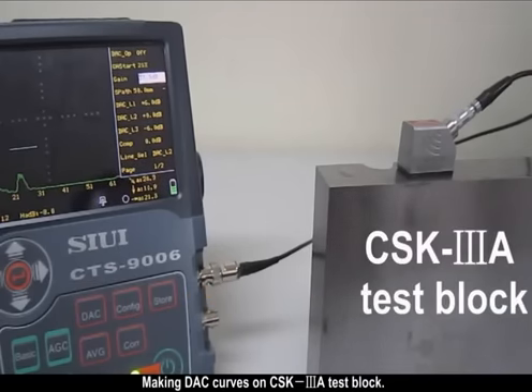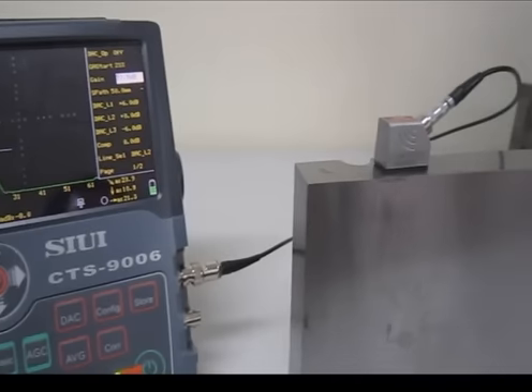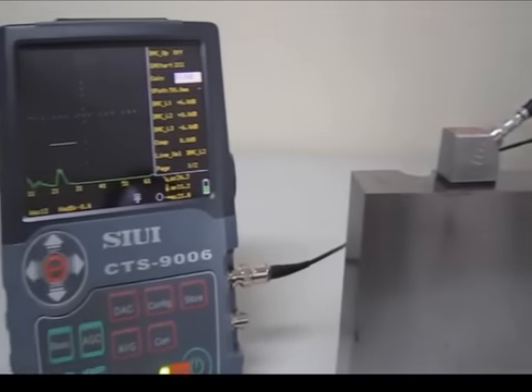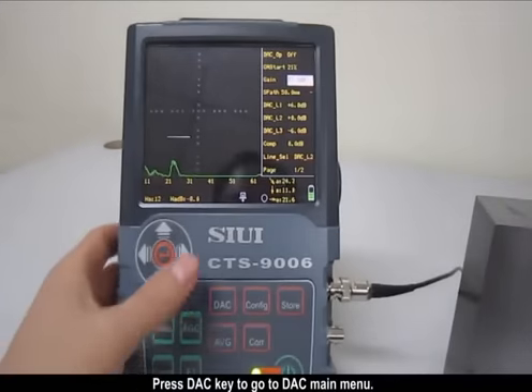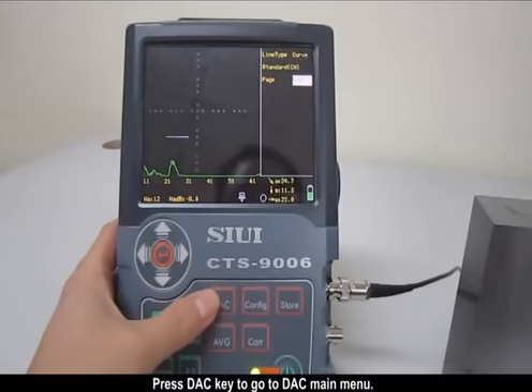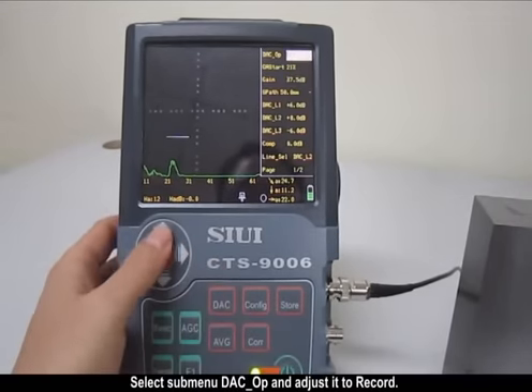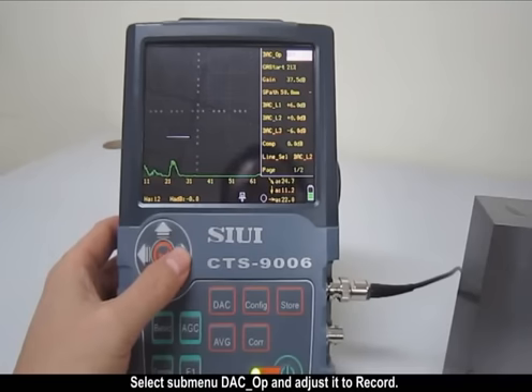Making DAC curves on CSK3A test block. Press DAC key to go to DAC main menu. Select submenu DAC operation and adjust it to record.